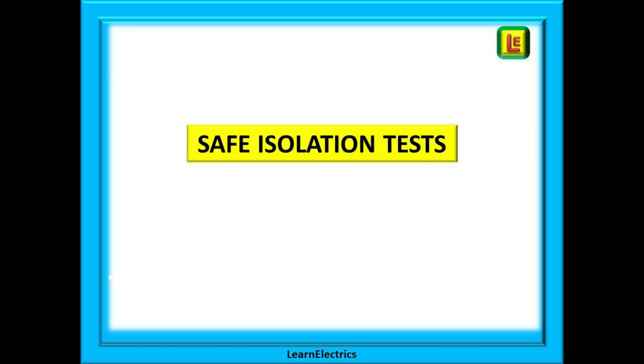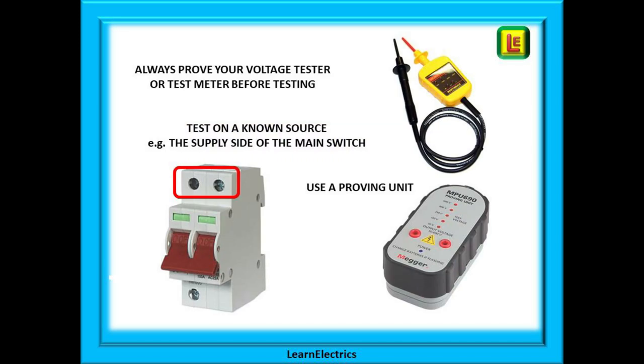We can look now at the safe isolation tests and what it is that we are testing. Make sure they have the correct equipment to test and isolate properly. Always prove that your voltage tester is functioning correctly. This can be done by testing on a known 230 volt source such as the incoming supply terminals at the main switch. We have already said that the supply side will always be energized. Or we can use a proving unit to check the voltage indicator. Whichever method you choose is fine so long as the check is carried out.